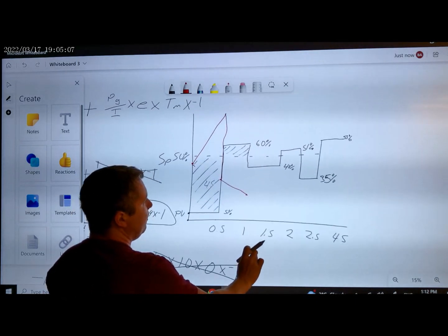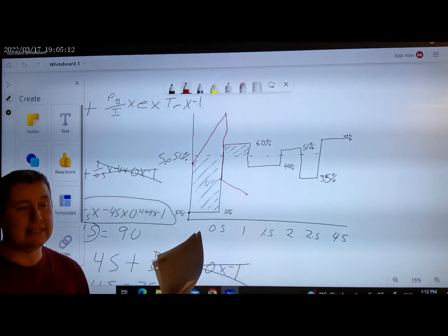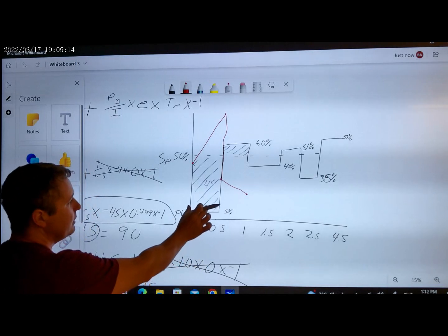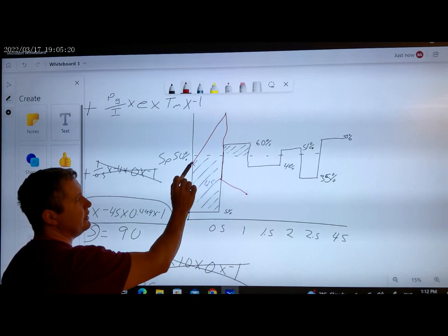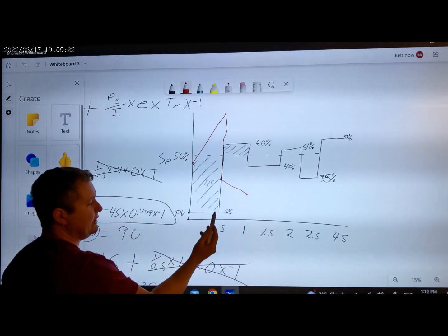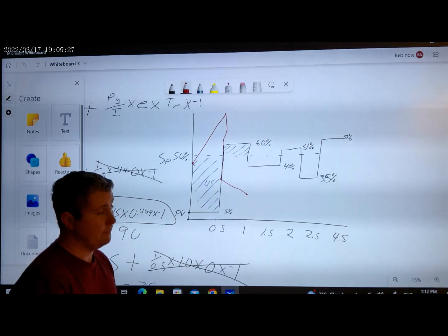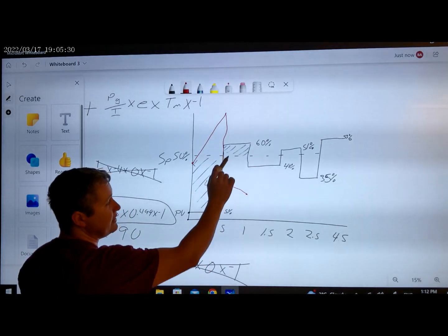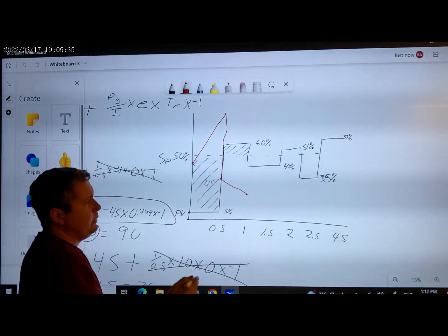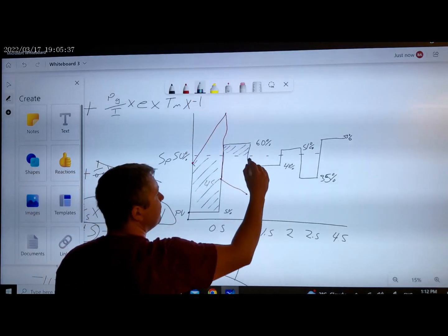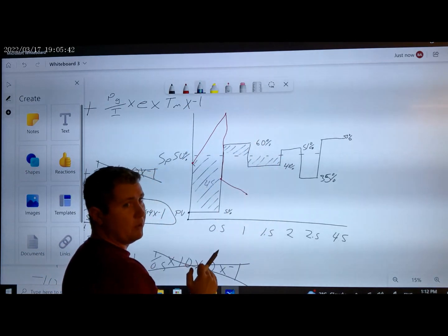When you look at this, and I want you to be able to draw it out just like this, because you see that when your process variable is below your set point, your integral is going to drive it up, trying to get your PV up in reverse acting. In direct acting, it would be the opposite. Then when it came above the set point, it tried driving it down to the set point. Well, what do we think is going to happen when we start doing this one? It's going to try driving it back up, right?